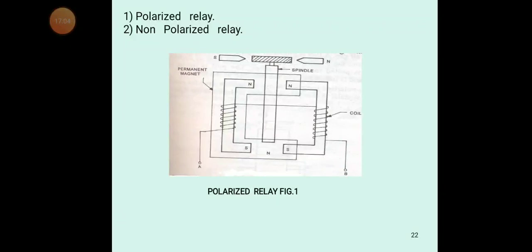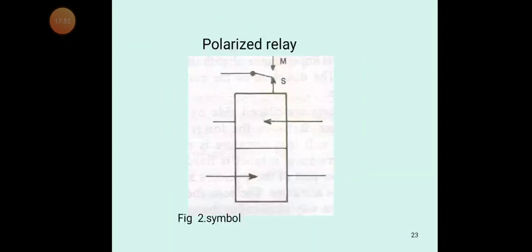Now we discuss the second classification — polarization. We have two types: polarized relay and non-polarized relay. In the polarized relay, you can see the figure — there is a permanent magnet with south and north poles, and coils. The magnetic effect of the permanent magnet is superimposed with the magnetic effect of the operating current. The direction of the current determines the position of the armature.